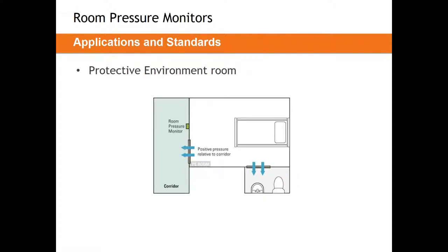Protective environments are essentially the exact opposite. The people in these spaces have a compromised immune system — their body cannot handle other diseases or anything that might be present in a hospital. So we need to isolate them from the rest of the hospital by blasting air out of the space. Protective environments are positively pressurized. The room pressure sensor should typically be right above the door, with the monitor located just to either side, clearly visible to those coming and going.